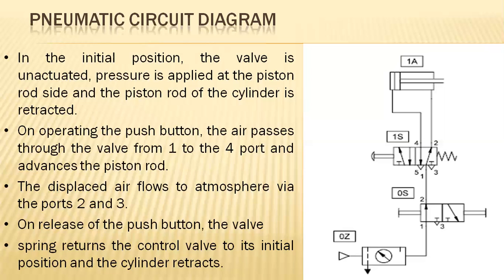So this is a simple piston and pneumatic circuit diagram in which the compressor compresses the air and supplies it, and the FRL unit plays an important role in the filtration of this pressurized air, lubricating and regulating. In the first DCV, the nominal pressurized air is accessed by maintaining a set pressure and enters, and when the first position is highlighted, it will connect and move into the forward motion, and the returned air will be released to the atmosphere directly.